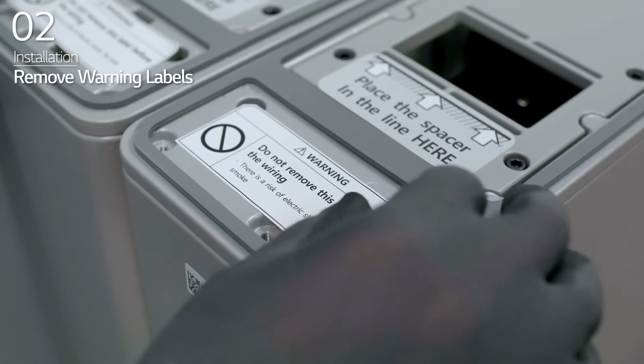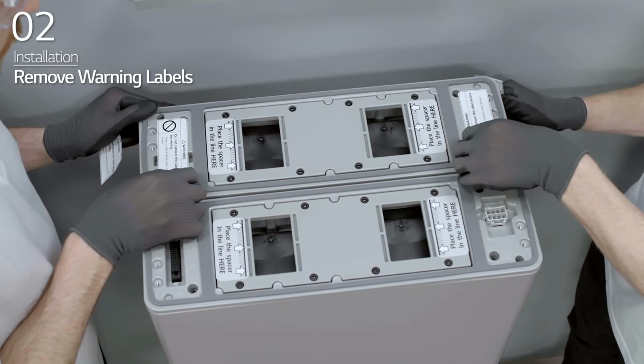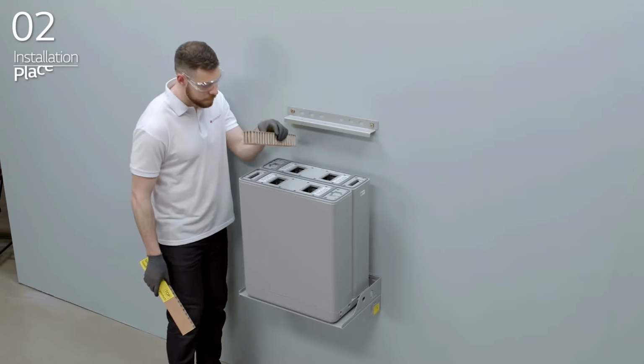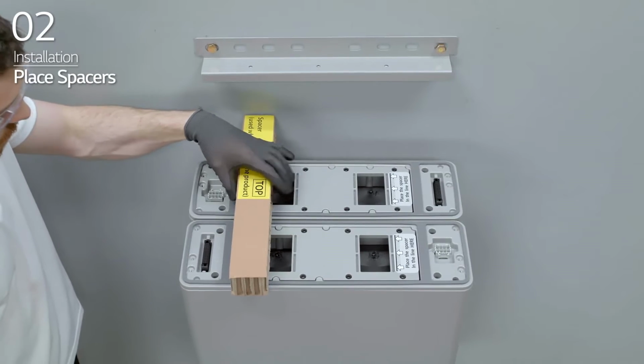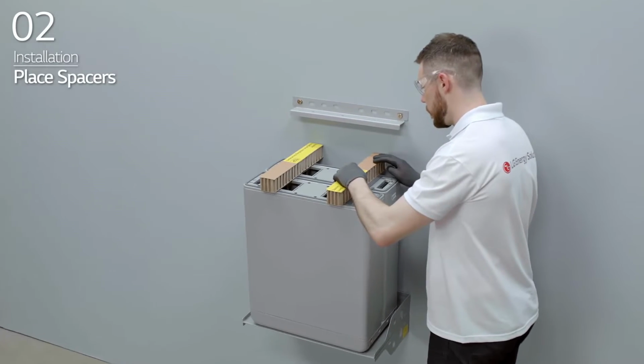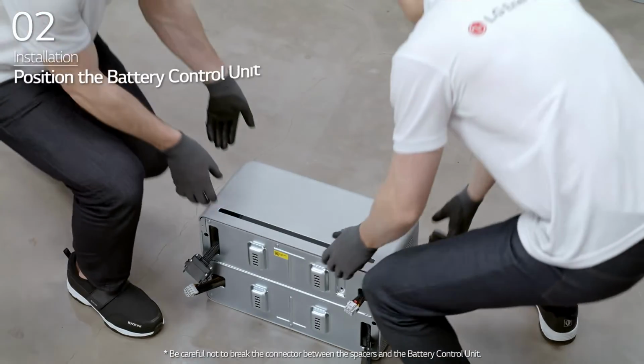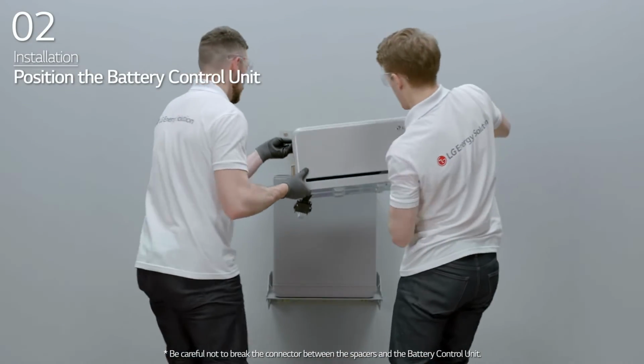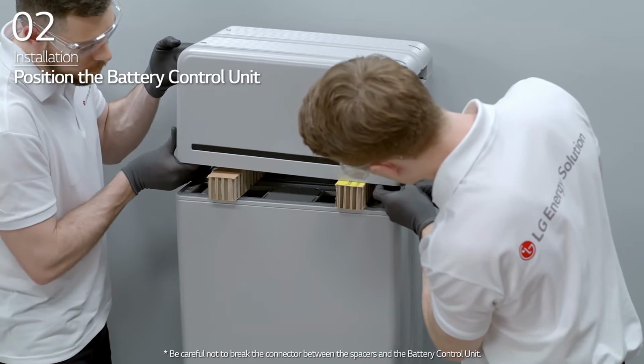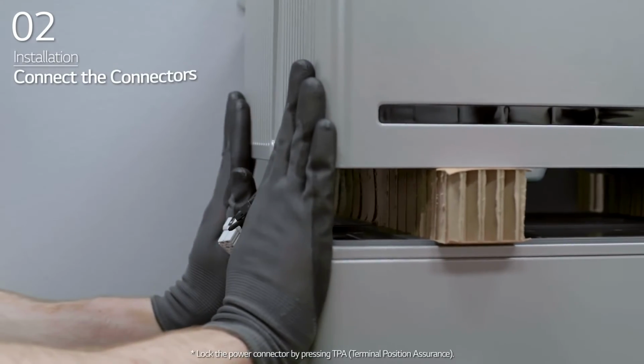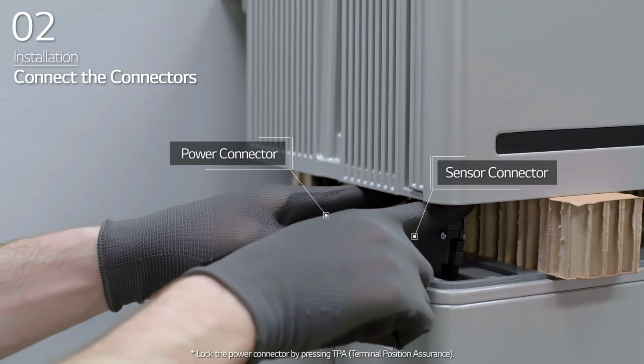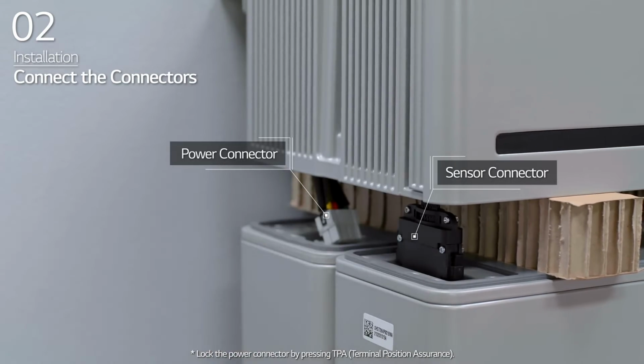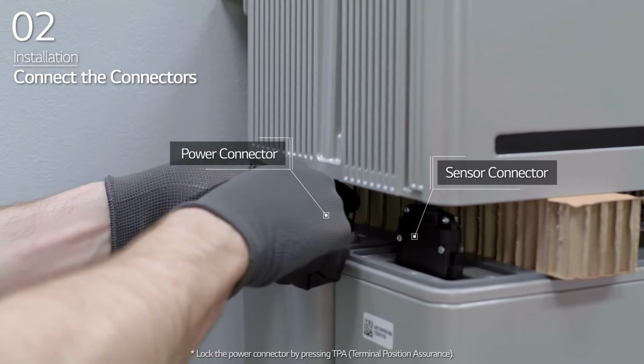Remove the warning labels from the battery modules. Place the spacers at the positions marked by the labels on the battery modules. Place the battery control unit on top of the spacers. Then, connect the 2 power connectors and 2 sensing connectors until you hear a click.